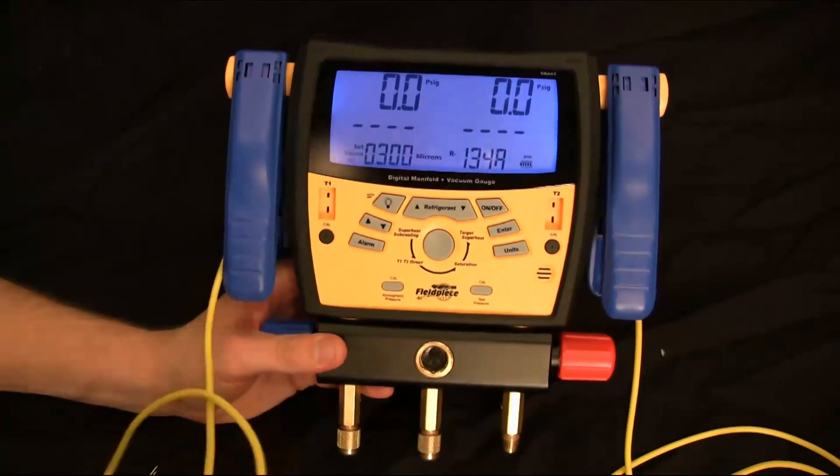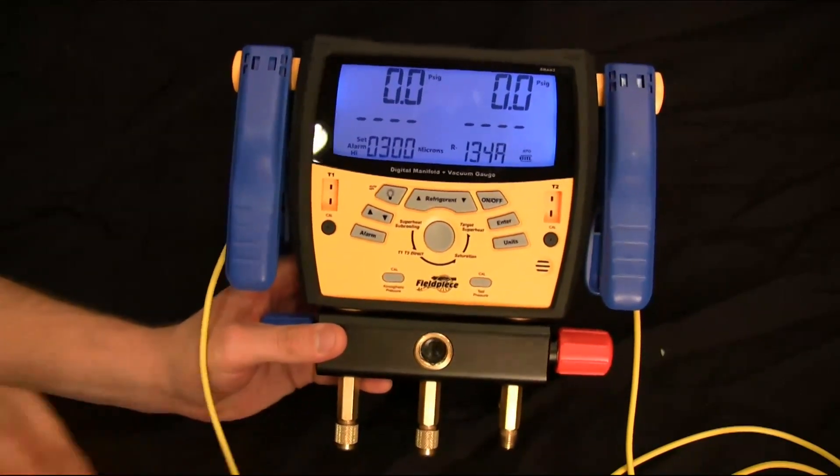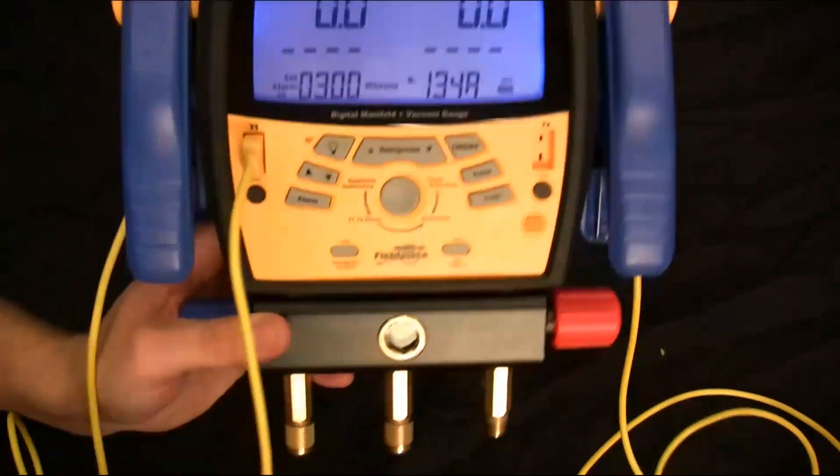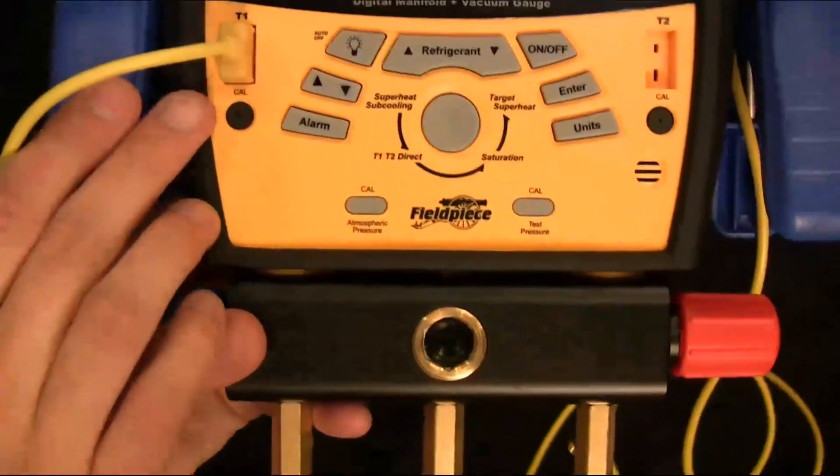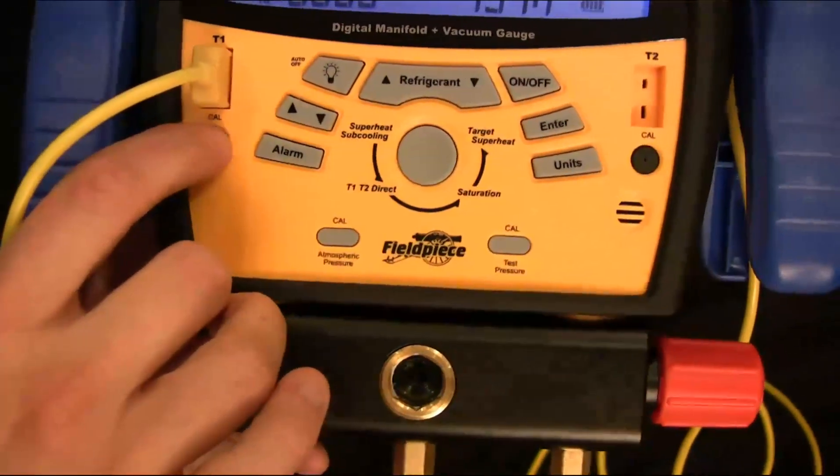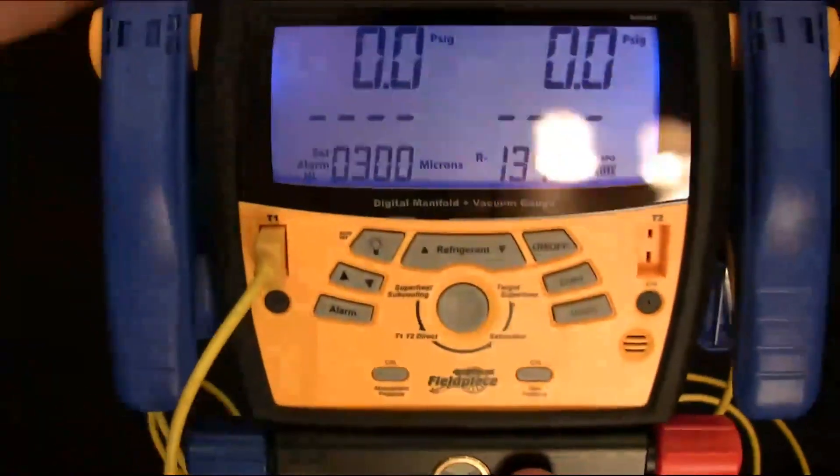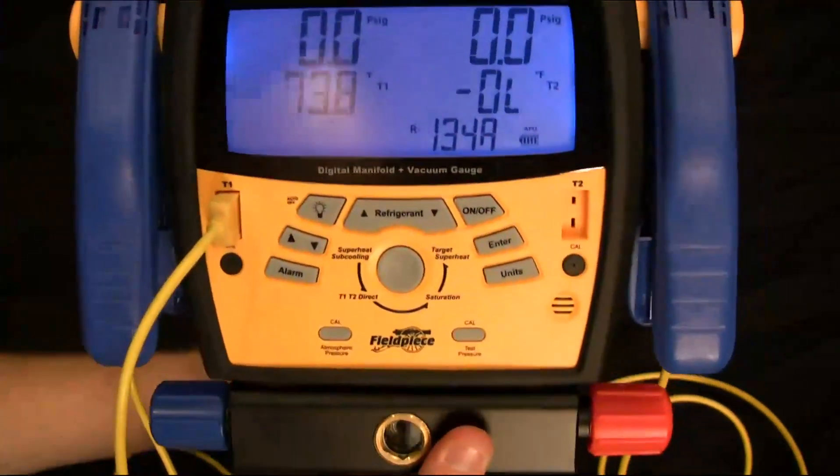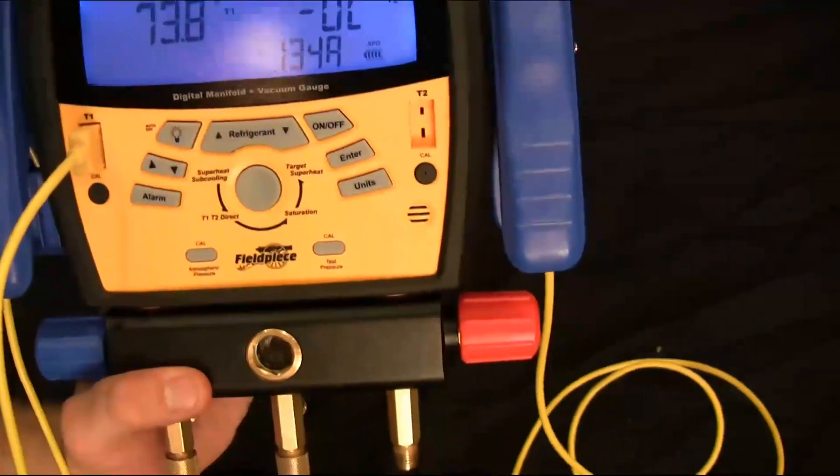Now to calibrate the thermocouples, we have two calibration pots, one for each. What you want to do is just typically do it to ice water or to a known temperature that's already calibrated, but just twist the cal pots and that will adjust the temperature. And you should do that in T1, T2 direct mode. And that's how to calibrate it.